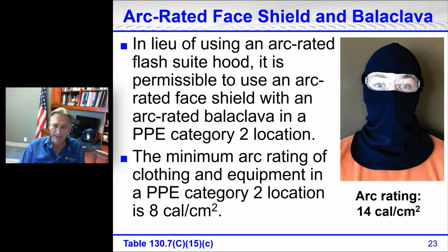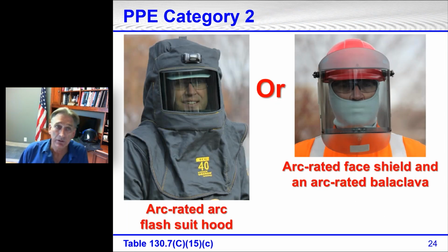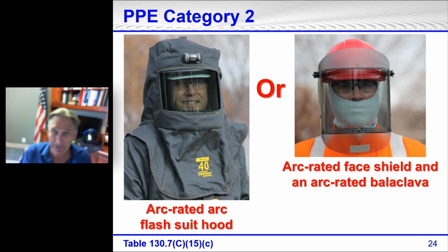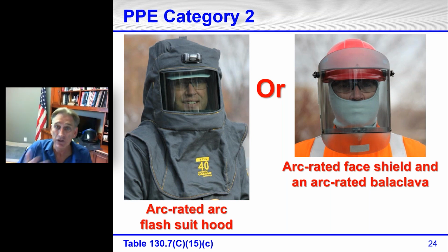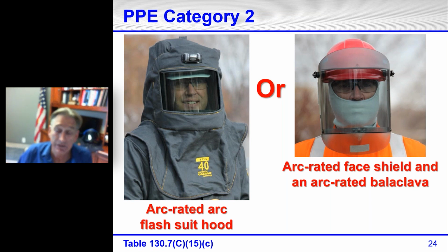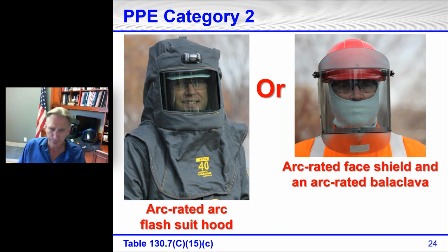All right, so we've got an arc-rated balaclava. In a Category 2 location, we could either use the hard hat with face shield, and I love these face shields and the clothing and equipment from Oberon. They were the ones that first came out with this, and they called it a true color gray. It is a gray face shield as opposed to the yellow-green face shield that came out first and was out forever, and even the hoods that were so dark that it was so difficult to see out of them. But we do have an option for Category 2, one or the other.